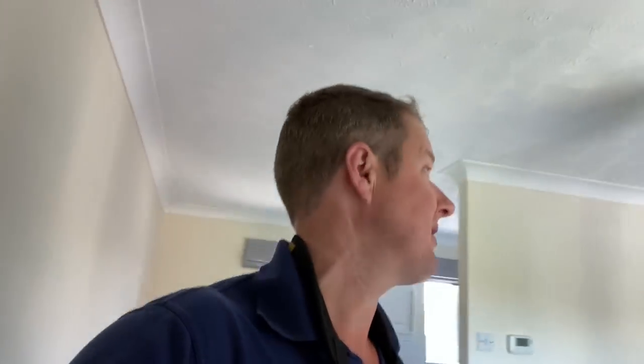Right, so just a little update. I've been busy testing this R2, I've literally been around every single light. There's so few of them, it just makes sense to do them all. So I've tested every single light, every single switch, every single socket for R2, and any other exposed metalwork and things like that. Oh, the only thing I've not tested is this light fitting. I almost forgot. Let me just show you this one now and see what's going on.